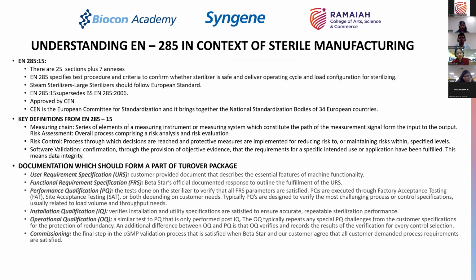This is a single page document, but I'm going to spend probably about 15 minutes on this. Okay. So EN 285 is a European standard which has been published into the industry. It's been revised in 2015, and I think there is a subsequent revision which is awaited this year or next year. Though it's a European standard, and there is an equivalent British standard as well, it is widely used across the industry, including the US FDA giving a cross reference to EN 285.